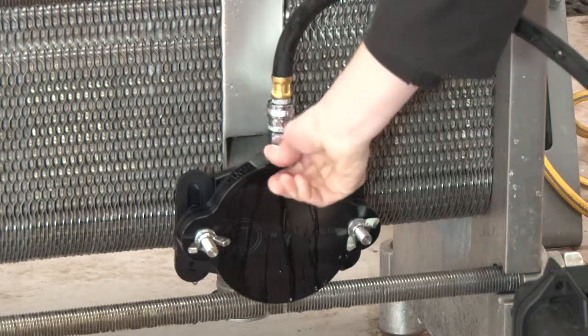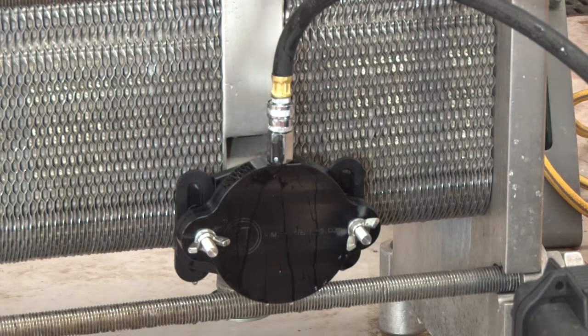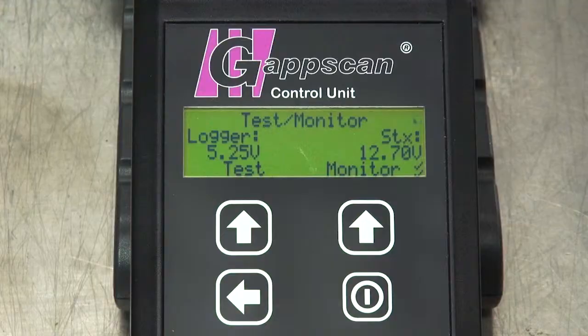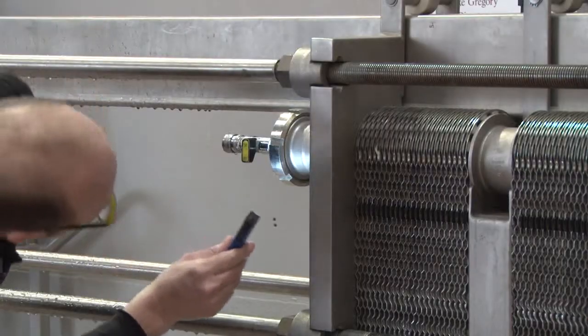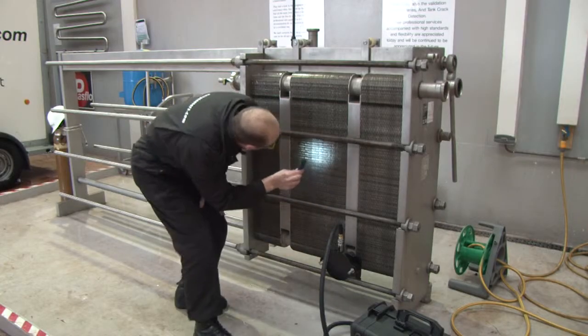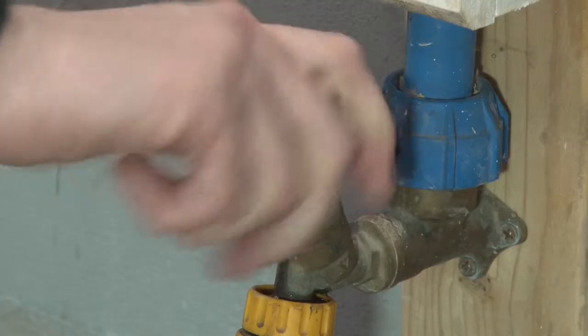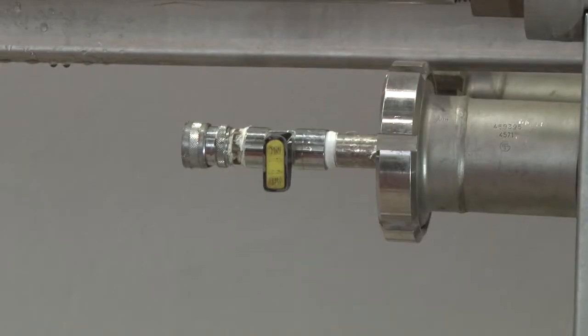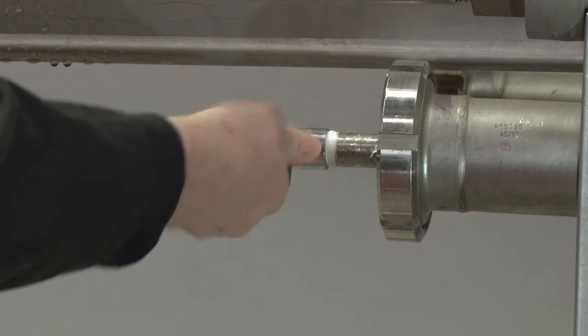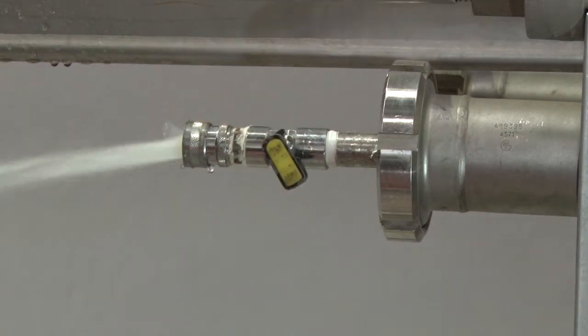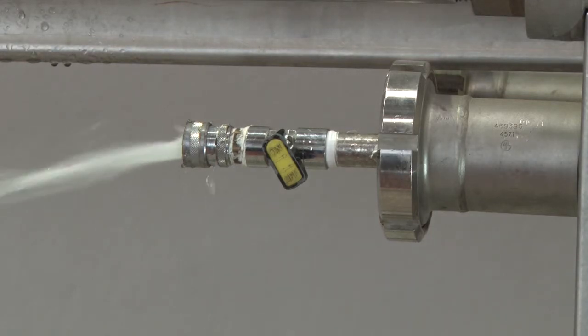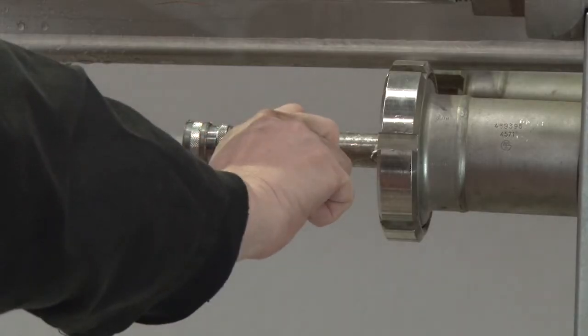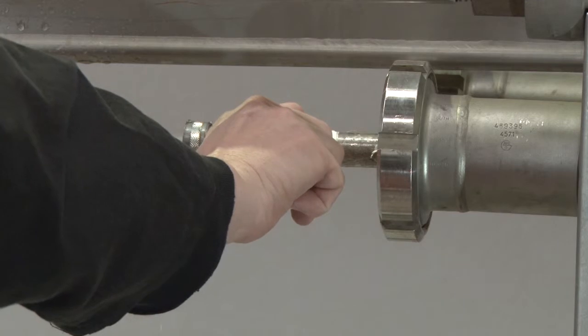Connect the outlet into the heat exchanger and open the valve. Put the control unit in monitor mode by selecting Mon Test, then Monitor. Look for any external leaks with a torch. Turn the mains water on full again. Open the outlet valve of the heat exchanger fully for 20 seconds to extract any air. Then reduce the valve to a trickle before closing it completely.